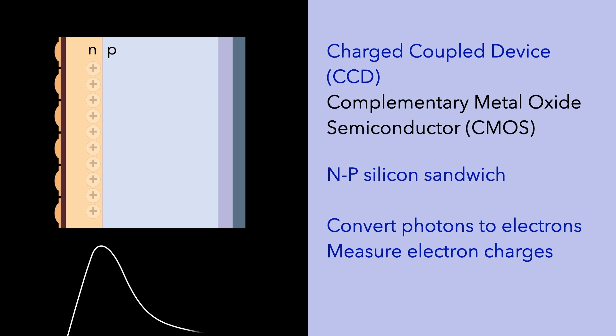This zone of slightly more positive charge will be important in measuring the electron charges that are produced when the sensor is exposed to radiation. The CMOS or CCD chip converts photons to electrons and provides a way for these electrons to be measured so that they can represent the pattern of photon attenuation and make a radiographic image.